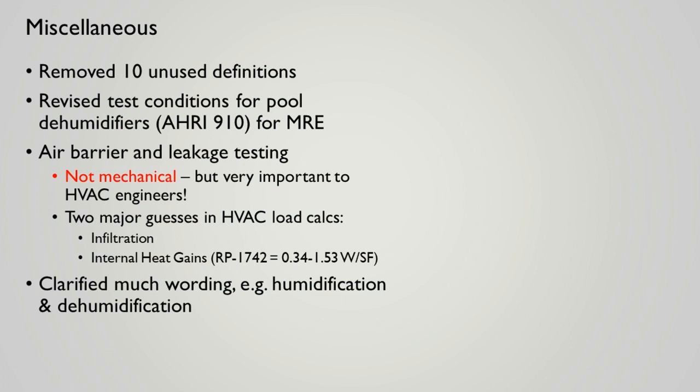I watch all the ASHRAE winter and annual meeting seminars, and if you have access to them, the winter seminar from 2019, seminar 52.1, covers interior heat gains from equipment quite well. So back to the issue of infiltration. I live in Wisconsin, and for zone heating loads, the infiltration guesstimate that I make often doubles the zone heating capacity, not the block heating capacity. I typically divide that by 2, figuring the wind only blows in one direction at a time.